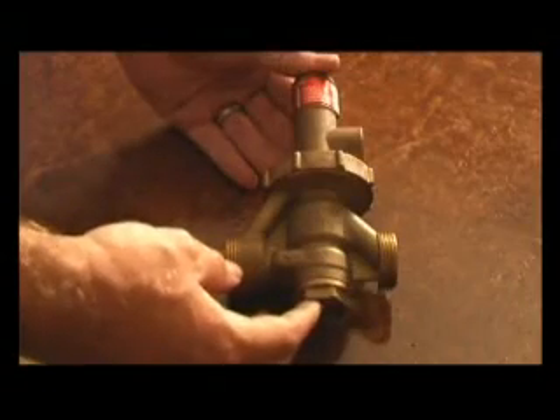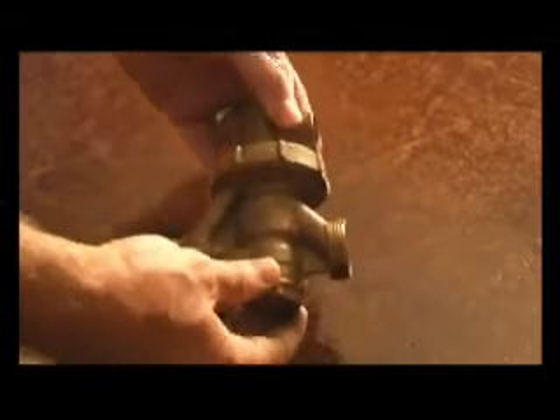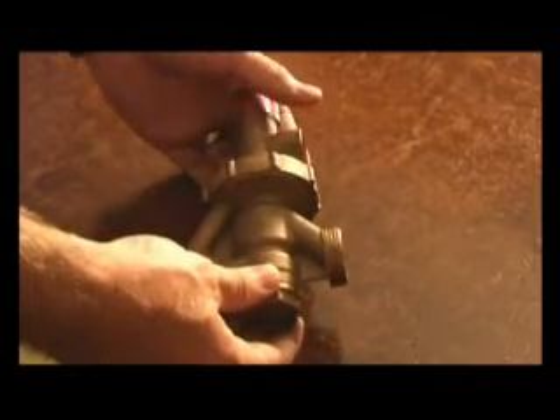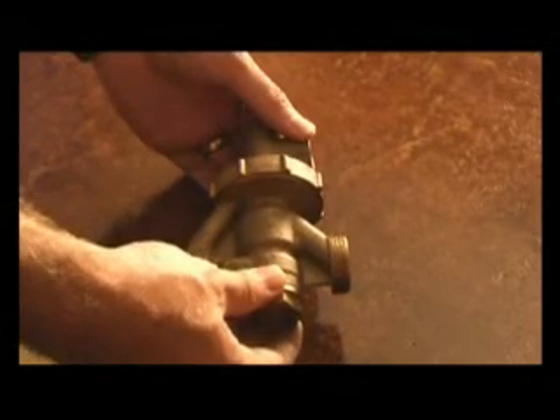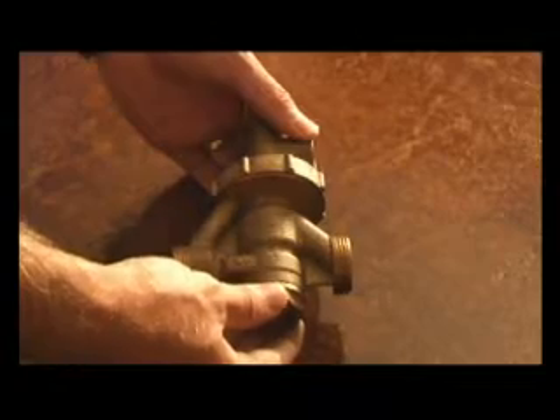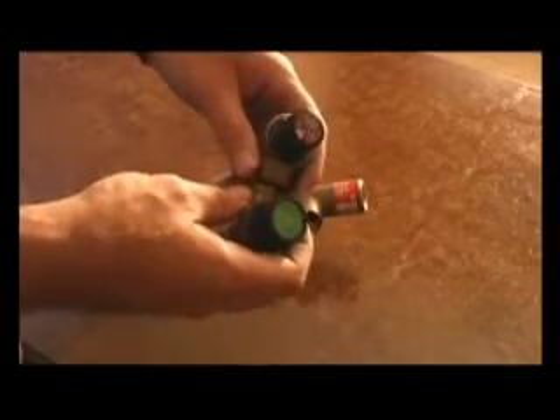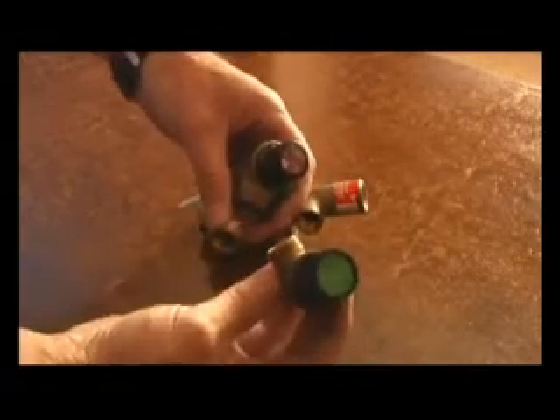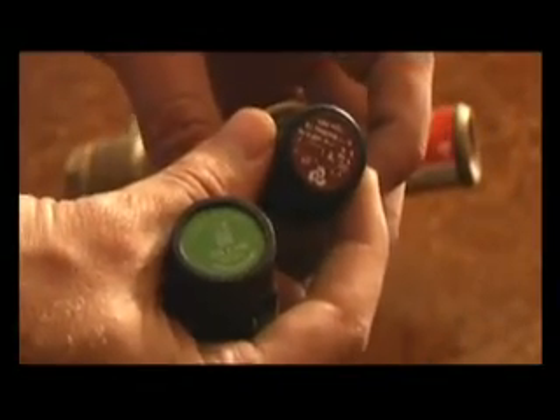On every hot water system, the hot and the cold water should be balanced. The delivery pressure between the hot and the cold should not differ more than 20%. All valves on a hot water system should be of the same pressure rating. In this case we have an expansion relief valve at 600 kPa, it's green, and on this side we have a T&P valve which is red, which indicates that it's 400 kPa. These valves cannot work together.